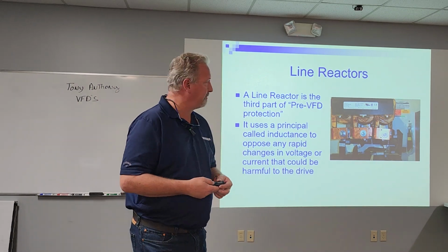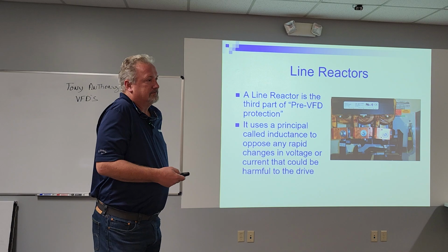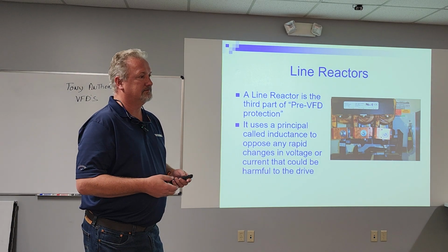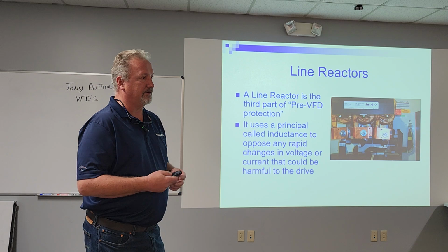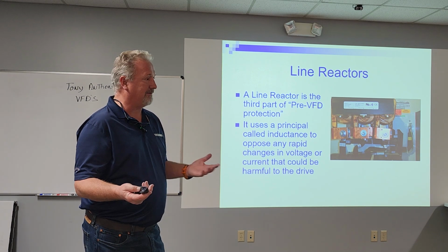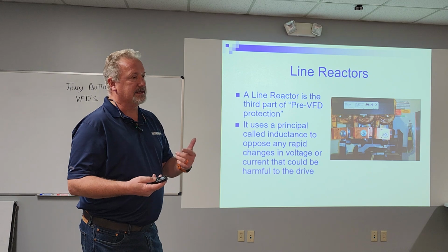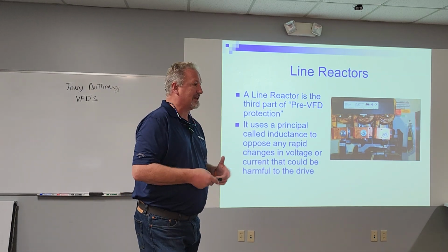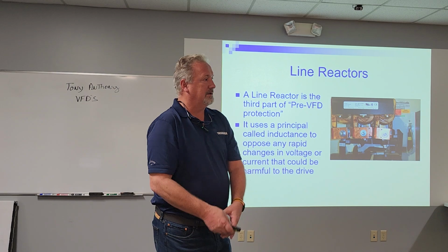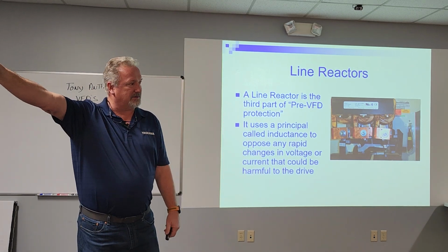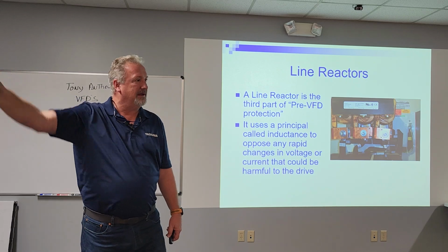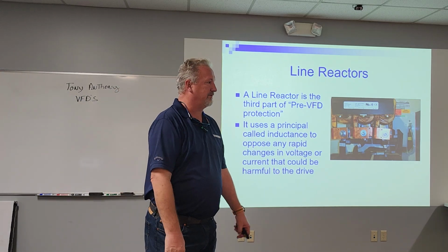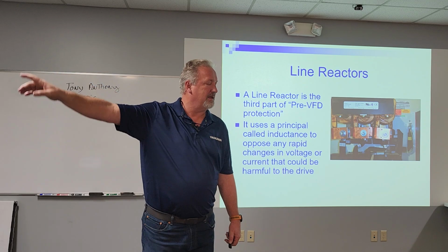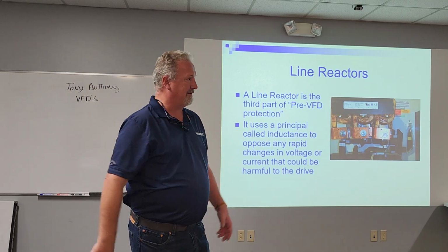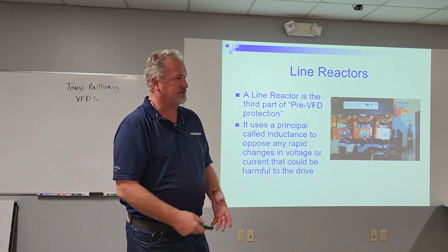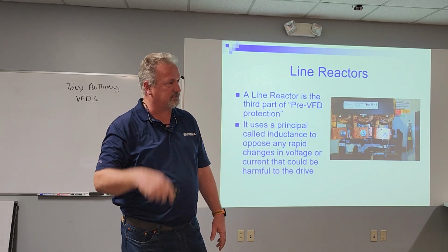No. We need a true RMS reading to get harmonics. Well, we put a scope on it for harmonics. And the spec actually is IEEE 519, which is what we have to adhere to, is 8% or 5% voltage and current distortion at the transformer feeding the building. So once again, the entire system, if you got one drive out there causing it, a 10 horsepower drive on the other end of the building, by the time it gets back to the transformer, you're not going to notice it. That's that guy 100 pumps away. But if you get 50 drives, all of a sudden, now you're going to notice that. And that's where you get that distortion. So you put a scope on it, and you can see that distortion.